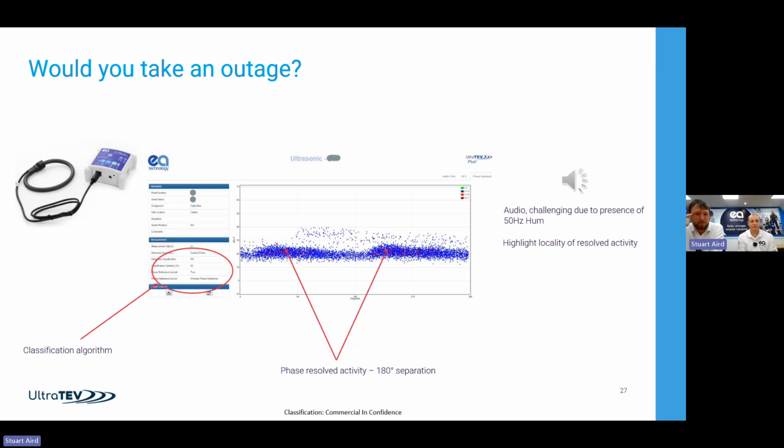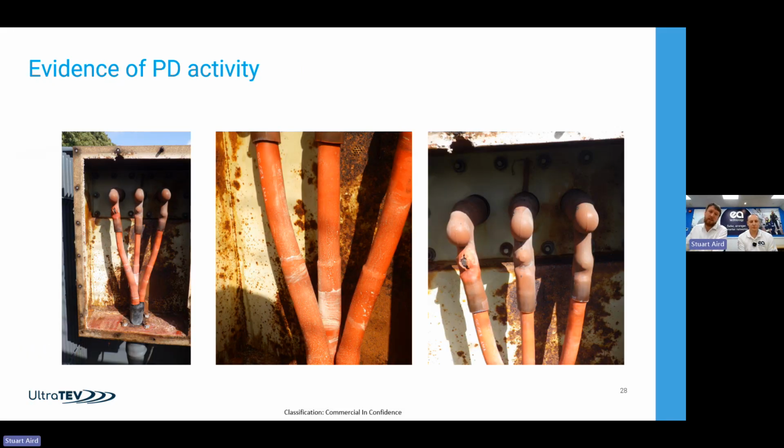Because one of the bolts has just snapped and it's all very shiny on the outside, this gear, we had the confidence to continue, and internally this is what was found. This isn't the same transformer as in the example picture at the beginning, but you can see the metalwork to the left of that first picture. It's well painted, it's well maintained. From the outside of this, you wouldn't have had any visual indication of any issue.